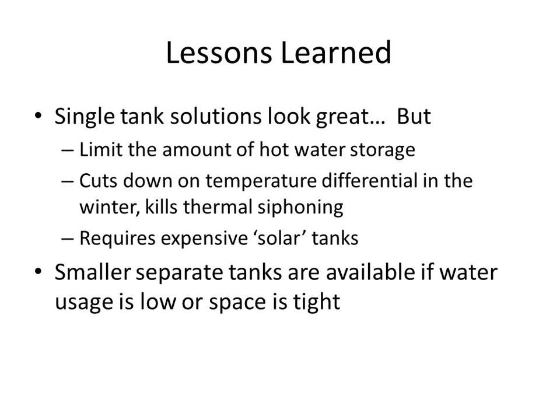What we've found is that going with what the industry calls the low boy tank, we can actually get these installations done in crawl spaces, under landings, stairwells, and things like that. Just because you don't have a lot of space doesn't mean a solar hot water system isn't going to work for you. If you don't have a dedicated utility room, and you're creative and can carve out just a little extra space, it doesn't even have to be full height, you can still get a solar hot water system into the home.